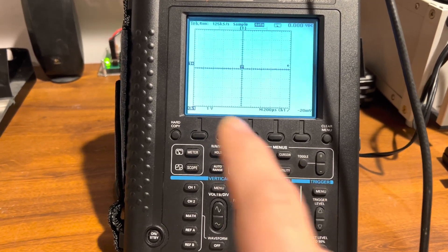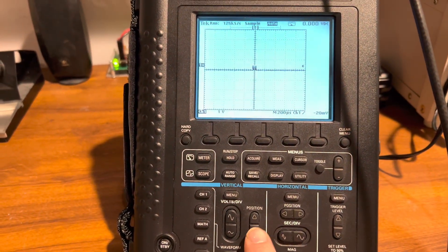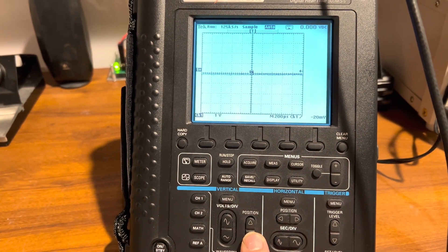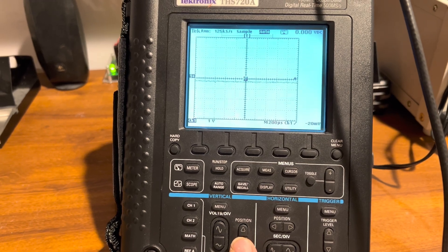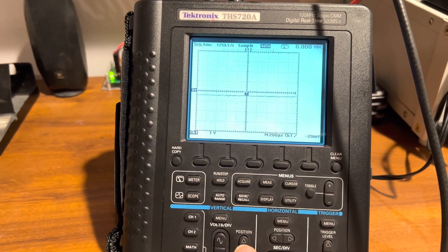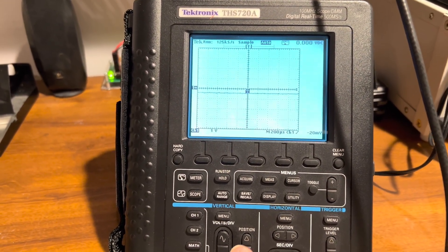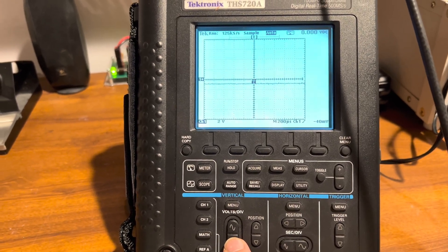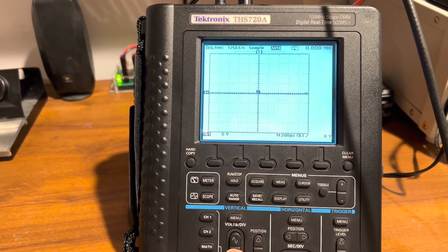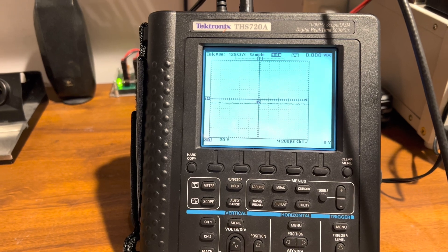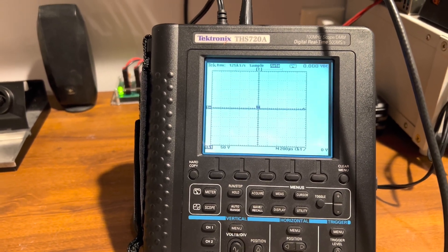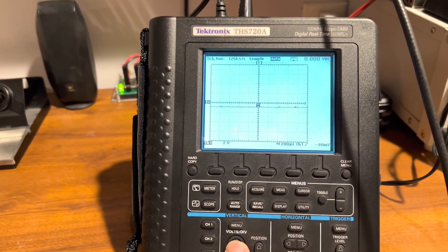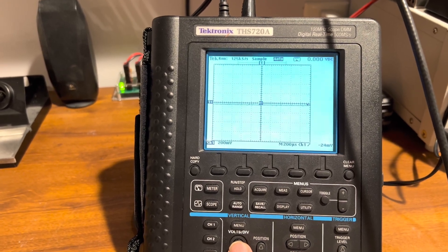It does have a problem and you can see right there there's a notable offset. Let's set this where it should be and you can see there's the DC offset. It does it on pretty much most of the ranges, not all of them—like five volts is fine, ten volts it's more pronounced. It could be the optic couplers; there's four of them on the actual channel itself.